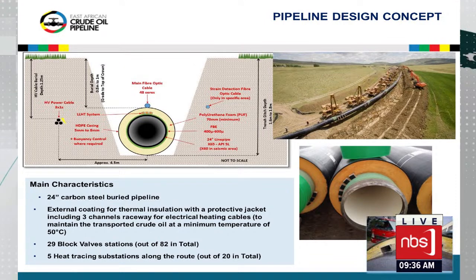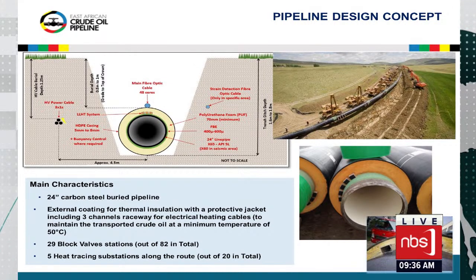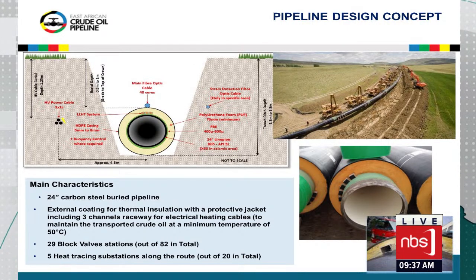To maintain the temperature always above 50 degrees C, we also need to install an electrical heating system all along the pipeline. For that, we will install heat tracing cable on top of the pipeline in the raceway shown in the picture on the lower right of the slide. To deliver power to this heating system, we will lay down high voltage cable parallel to the pipeline, connected to the heat tracing cable at dedicated substations along the pipeline route.